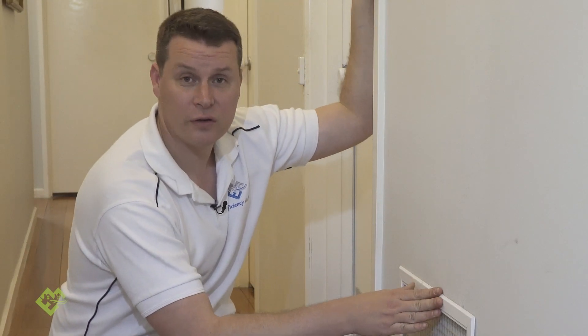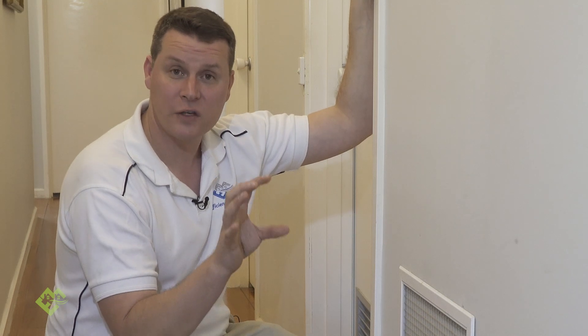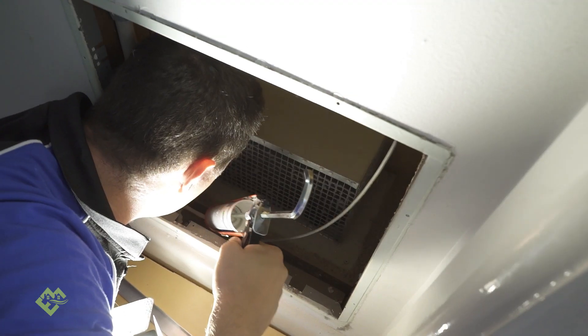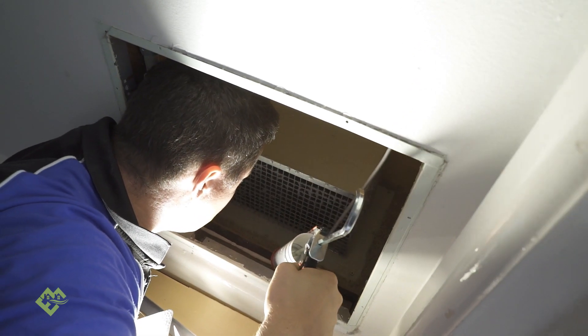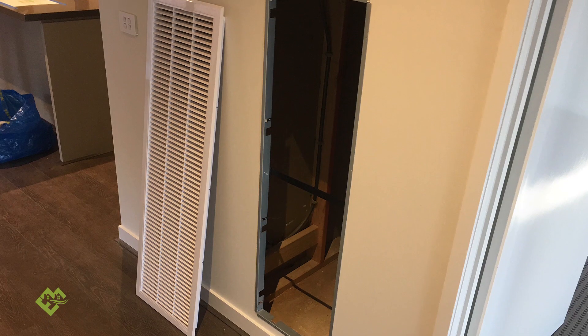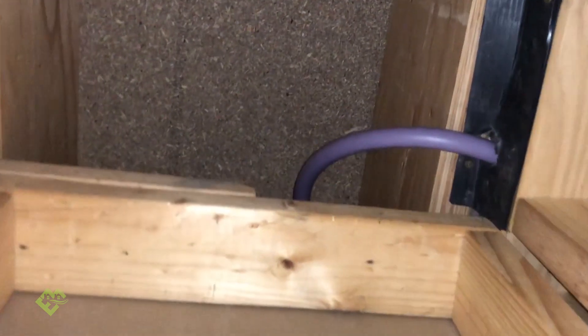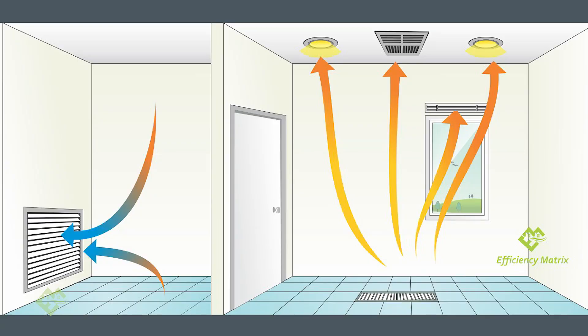A leaky return is a little bit similar to driving your car with the heater on and your window open. It's really important that the return is as airtight as possible, because whatever air is getting sucked in directly from outside via the return, you will be pressurizing on the supply side to push outside of the building envelope.